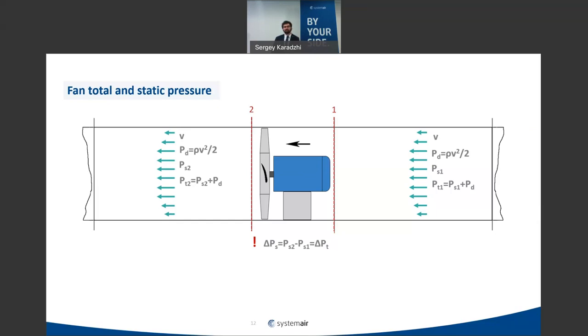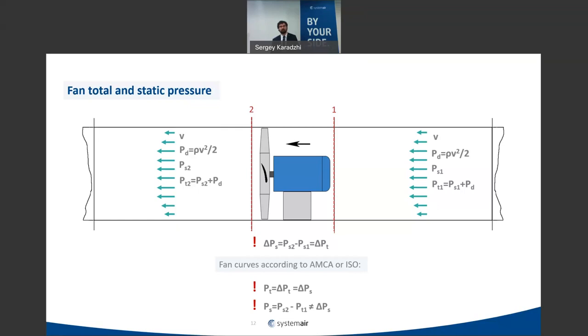A common problem is that customers mix up the static pressure difference across the fan with the fan's static pressure as defined by ISO standards. According to ISO, the total pressure of the fan is the difference of total pressures on inlet and outlet. The fan's static pressure is the difference between static pressure on the outlet and total pressure on the inlet — which is not the same as the simple difference of static pressures. Fan static pressure should be used when the fan has a free outlet, as in Categories A or C.